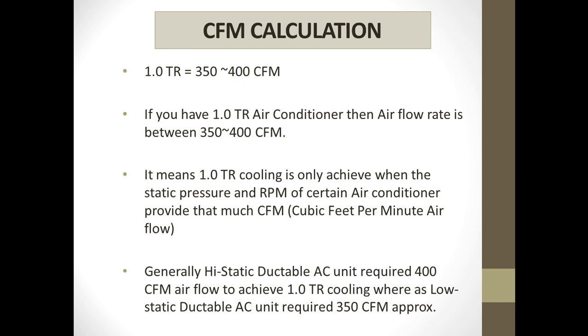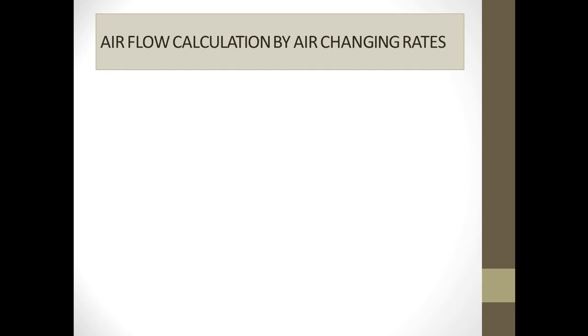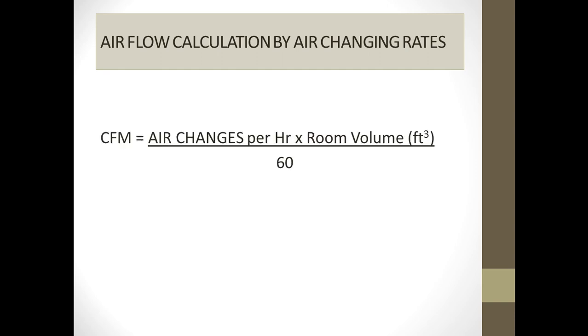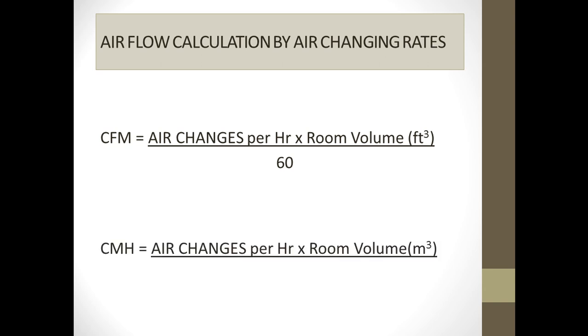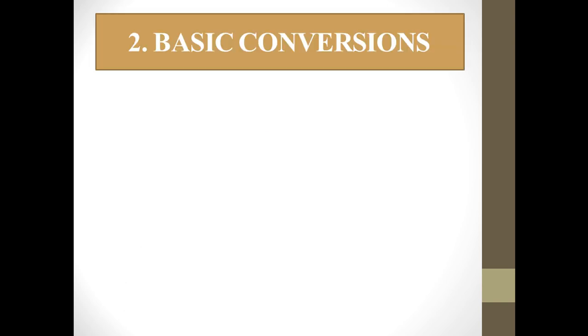Generally, a hi-static ductable AC unit requires 400 CFM airflow to achieve 1 TR cooling, whereas a low-static ductable AC unit requires approximately 350 CFM. For airflow calculation by air changing rates, the formula is: CFM = (Air Changes Per Hour × Room Volume in cubic feet) / 60, where 60 is the conversion factor from hours to minutes. In metric units: CMH = Air Changes Per Hour × Room Volume in cubic meters.